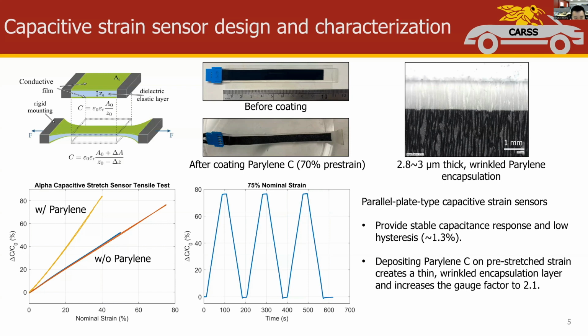To make a stretchable encapsulation layer, we decided to use Parylene first, since it's biocompatible and it has good hermeticity. We first pre-stretched the sensor and deposited Parylene C on its surface. Upon releasing the sensor, the contraction will spontaneously create wrinkled Parylene structures, as you can see at the right-hand side. Since the wrinkle structure can allow the sensor to maintain a constant width during stretching process, it actually increased the sensor's gauge factor from 1 to 2.1, which made our strain sensors even more sensitive to strain.